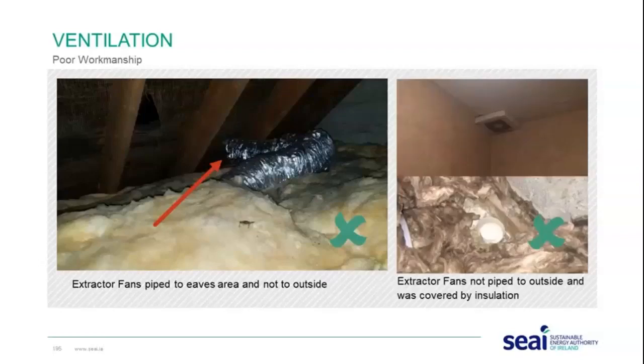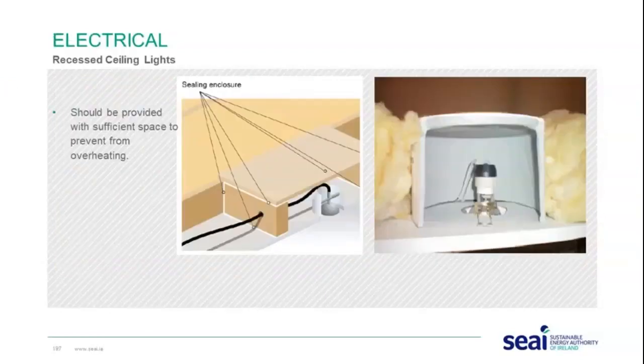An inspection example shows a fan in the ceiling that was covered by insulation when the roof space was entered. As an inspector, the check includes looking for fans in wet rooms to verify they are ducted to an outside source.